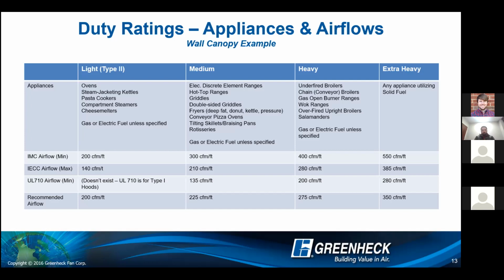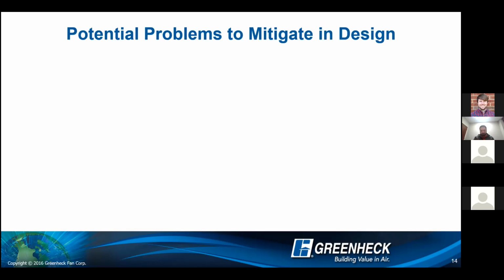So we've determined our airflow, we've determined the duct size, and then that's how we're going to size our fans. Makeup air is typically going to be sized to be 80% of exhaust. What problems could come up in this? Because once we have our airflows, what problems do you need to take into account? There's really not many. Designing a kitchen is pretty straightforward once you know your airflow, but there are some things to look out for. So what would those be?